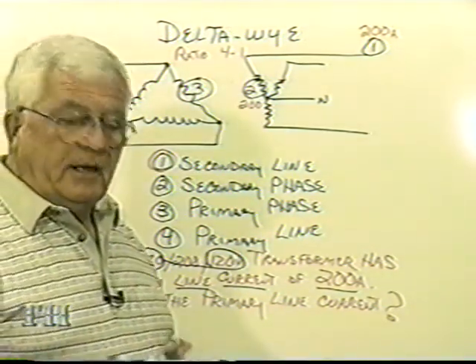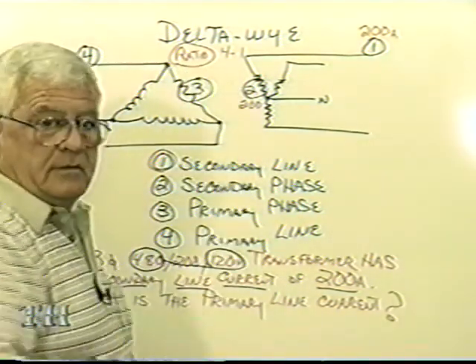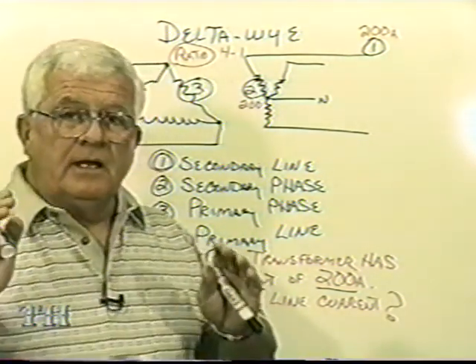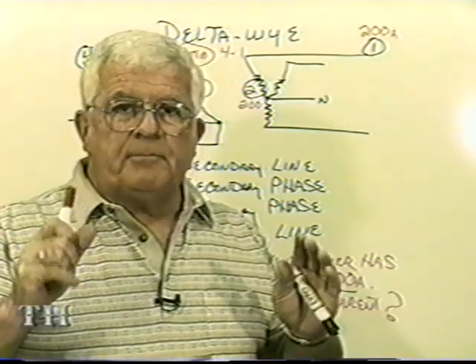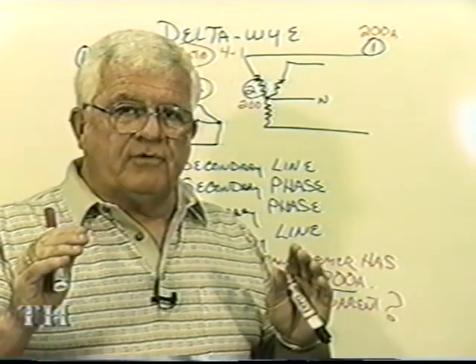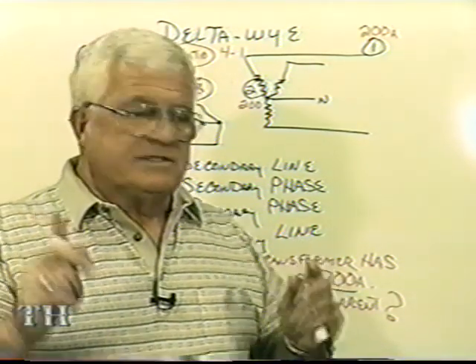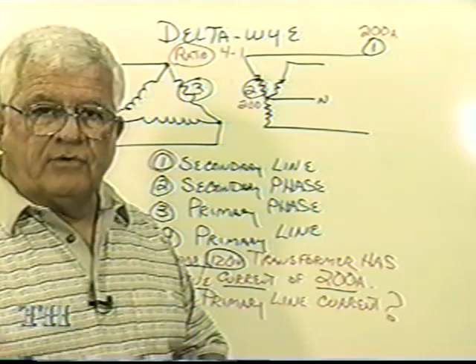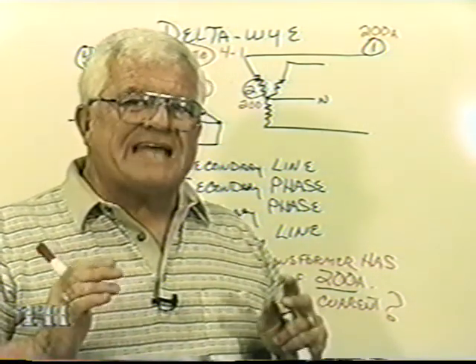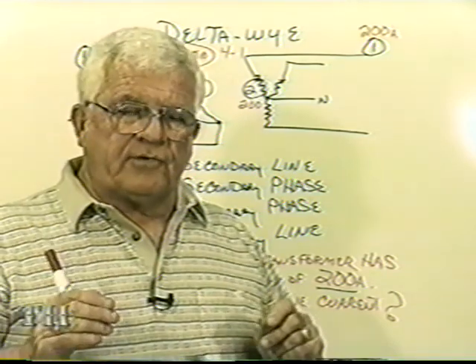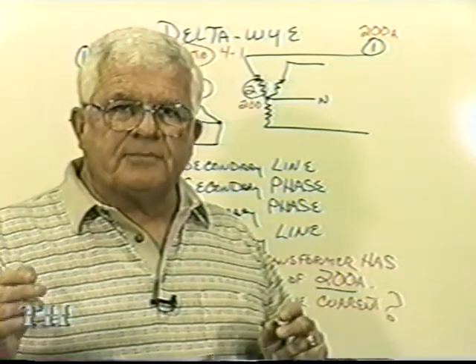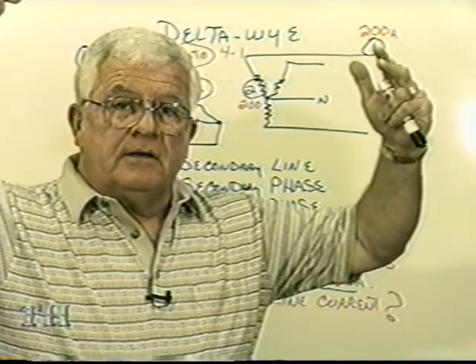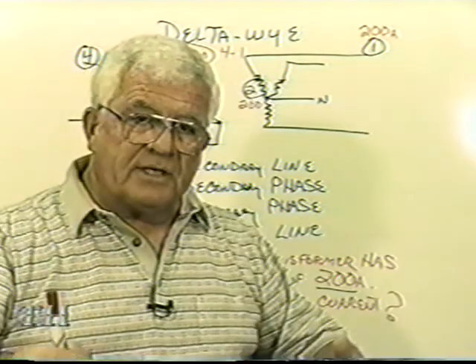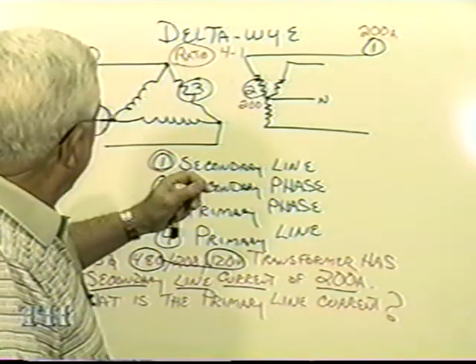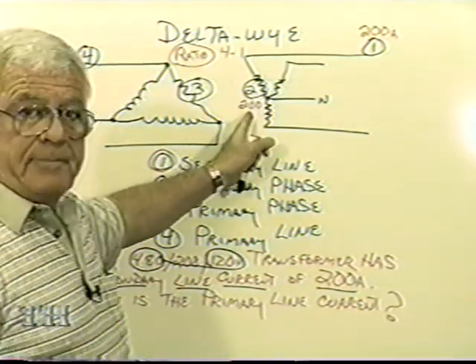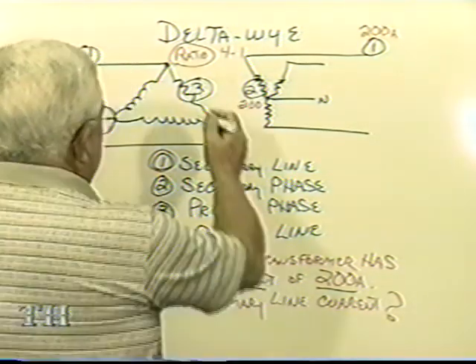Step 2 to 3, this is where the ratio becomes involved. Now, over there on that delta primary, I raised the voltage to 480. See, over here, in this coil, I only have 120 volts. I raised the voltage 4 times. What's going to happen to the current? We learned this in single-phase transformation: when we raise the voltage, what happened to the amperage? It went down. Well, if I raise the voltage 4 times, up to 480, what's going to happen to this guy? It's going to become 50.